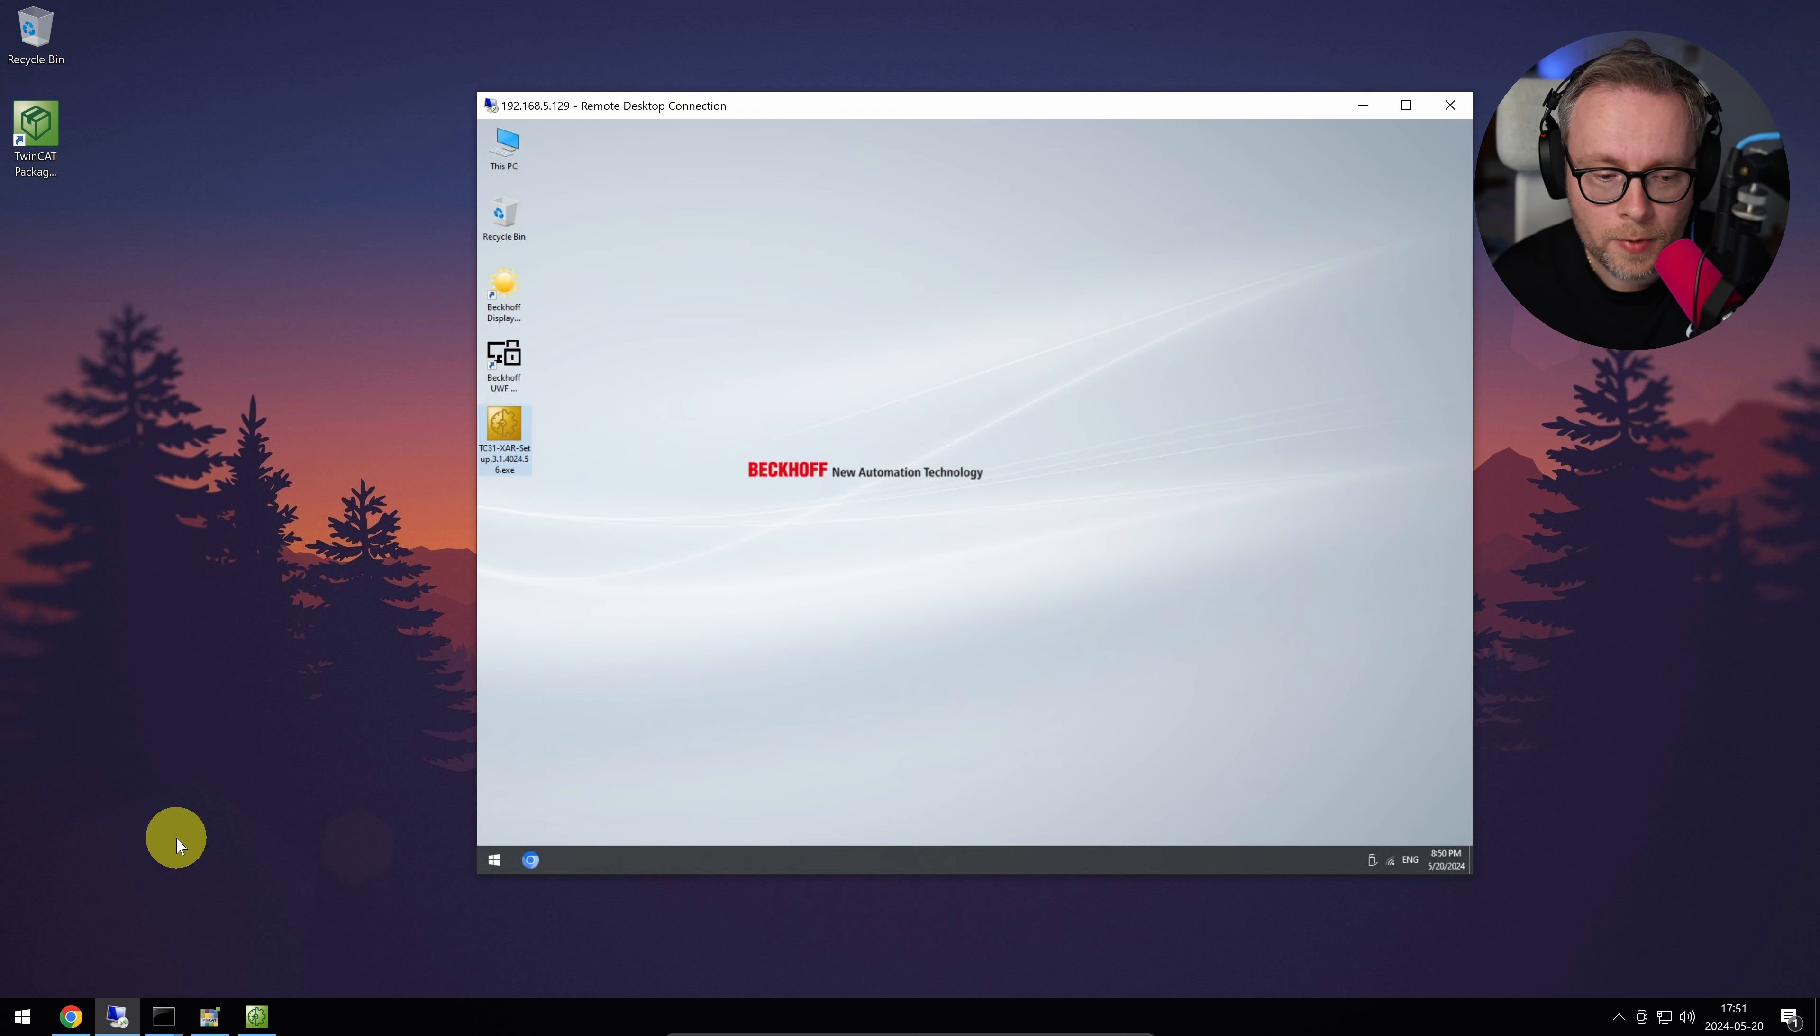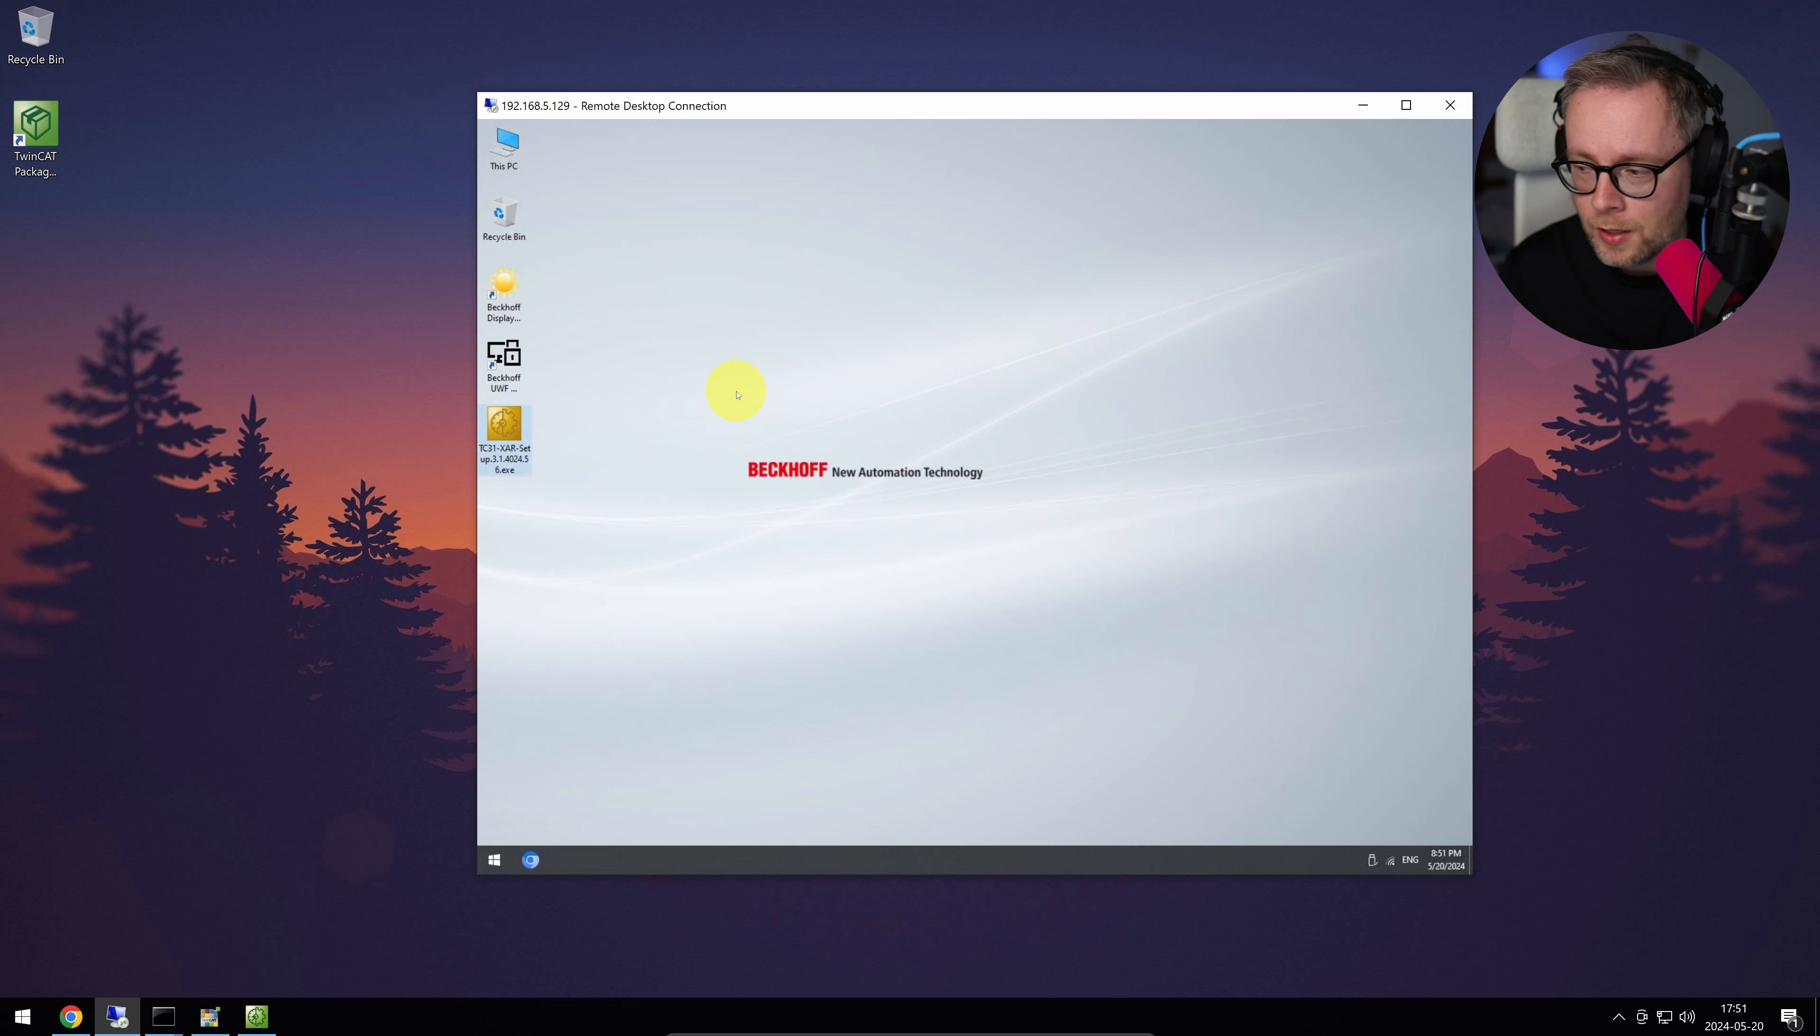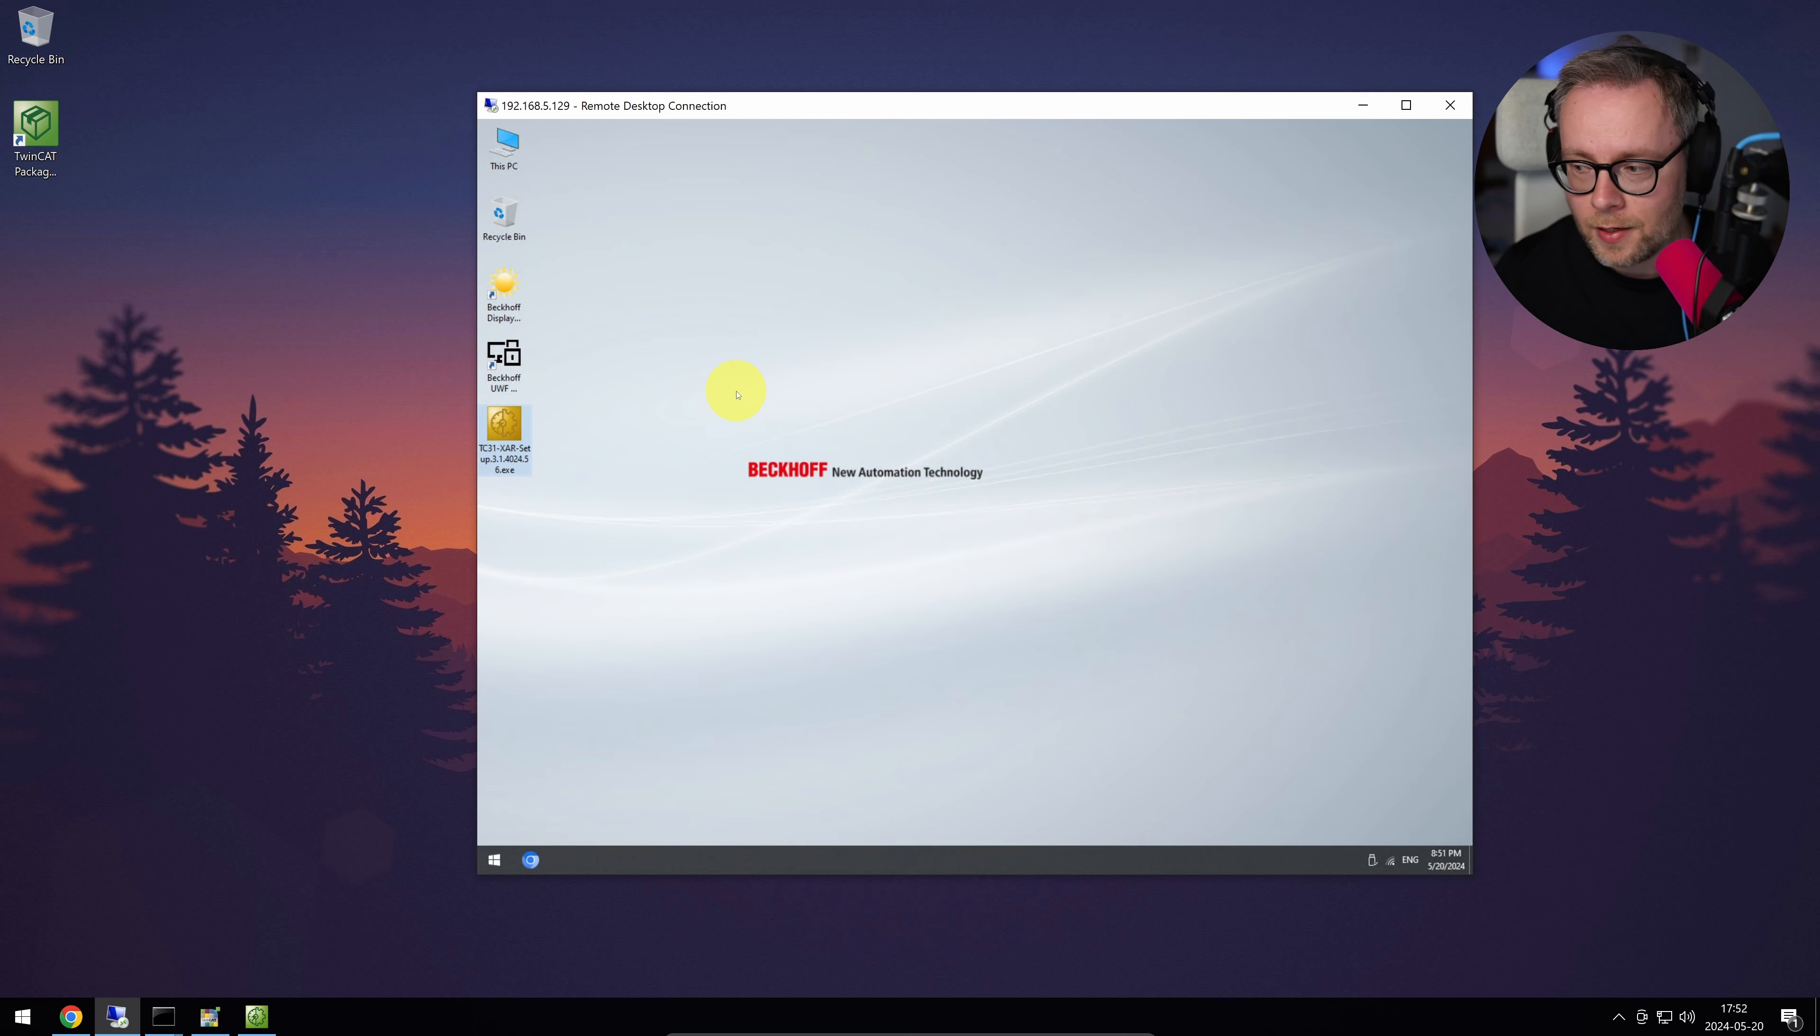The documentation here mentions some of the things that we want to know. But basically, what you need is that you need to have the package manager installed on the target device itself. So that's the big difference to how it was before. Before you had XAR. Now you have the package manager, install everything from there, everything that you might need. Now I hear you say, but Jacob, oh my god, how does it work? I mean, doesn't my PLC need to have internet all the time? Like the package manager, it's using internet to connect to the package server and everything. And no, you don't need to worry about that. You can create package sources locally on the PLC. So using a USB stick or using the local hard drive, whatever. You can download, pre-download all packages, put them on a USB stick and put them inside the PLC and say, here are my packages. Please install the XAR from here. And that's what we're going to do today.